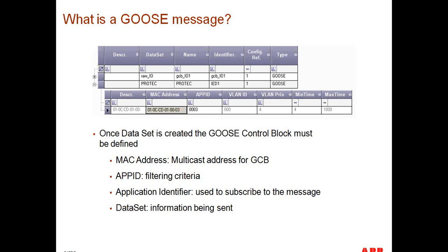But the destination is what changes, and the destination is in the form of a multicast address. The way a multicast works, ignoring any type of virtual LANs, is that a message goes out, and any port associated to the switch where the relay is sending that multicast will have the capability to listen to or see that particular message. So if you have a 24-port switch, for example, with no virtual LANs configured, and a device sending a multicast or Goose message, you could connect your computer or the relay that's supposed to listen to that message to any of the ports, and the association will still be valid.